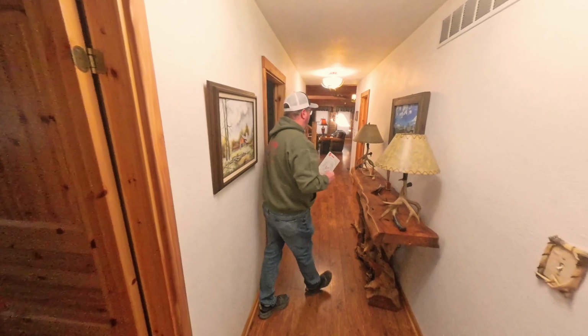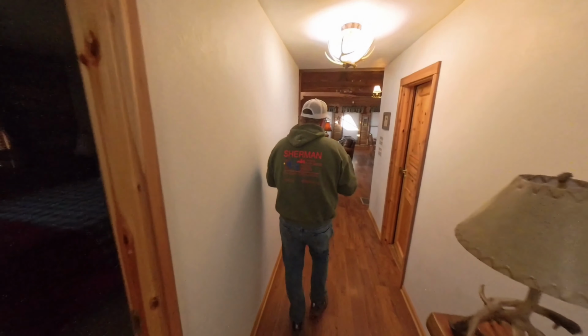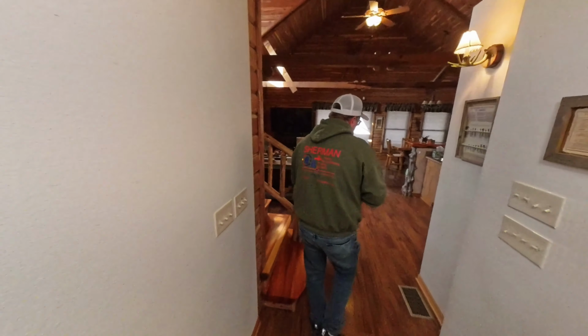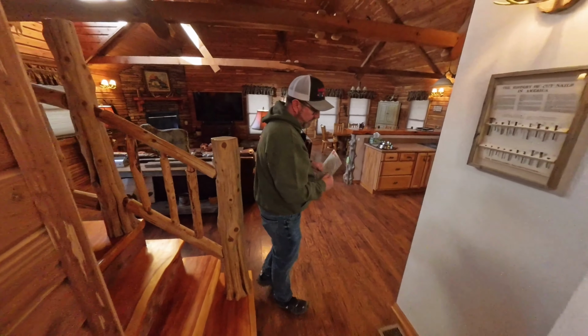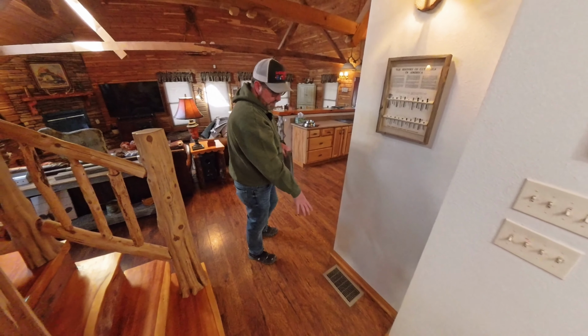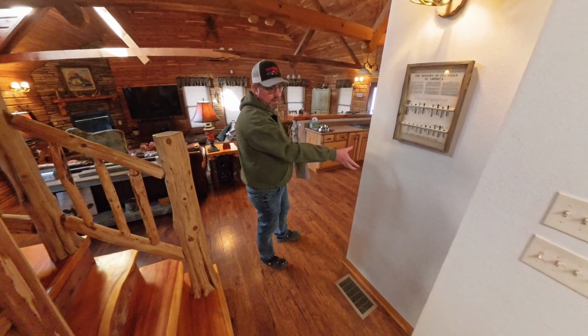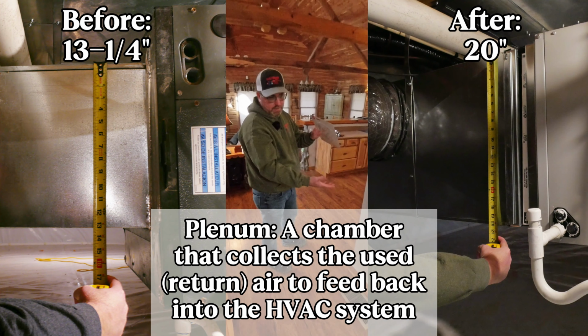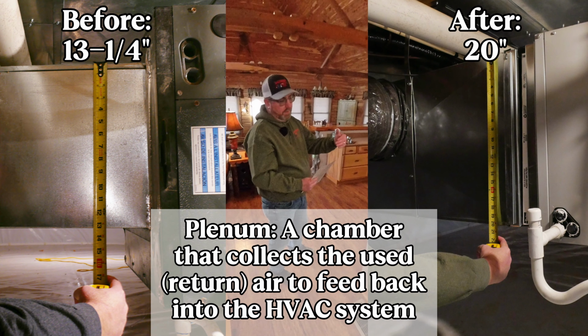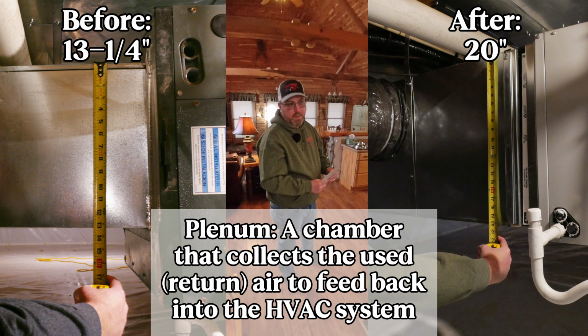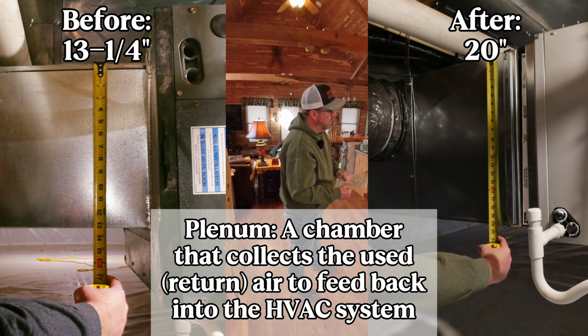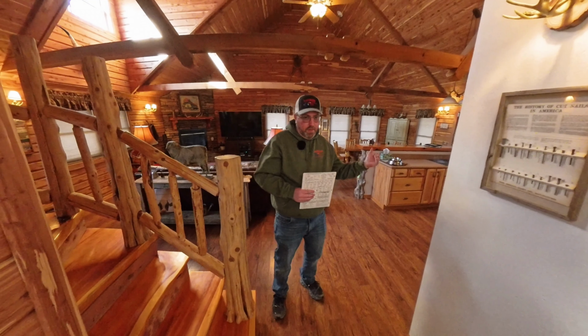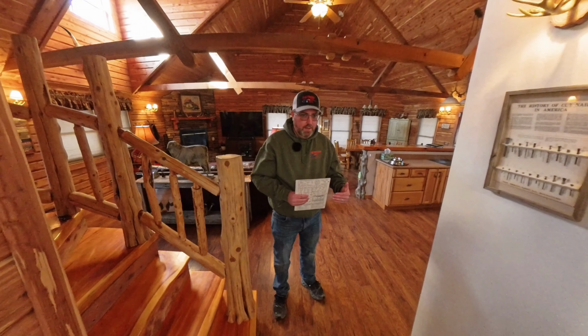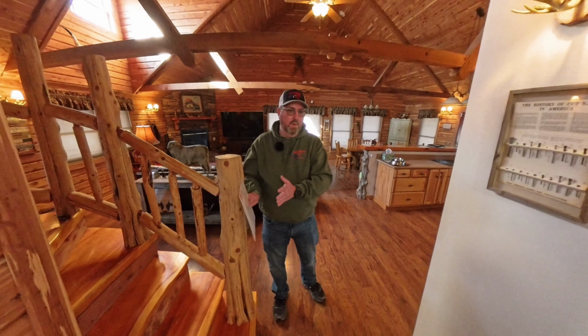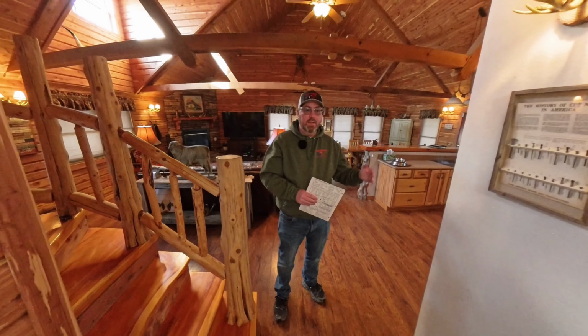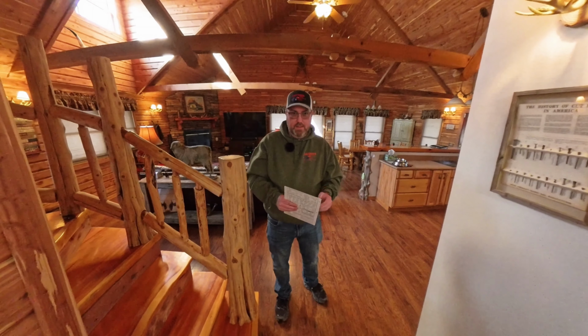So what we wound up doing is out here in this nice big open area, we added a floor return here, which has its own separate duct that goes back to an enlarged return air plenum, which we changed also because the return air plenum coming to the unit was not large enough to carry the CFM to operate the system properly. So we need to bring back as much, if not more, return air than we're putting out.